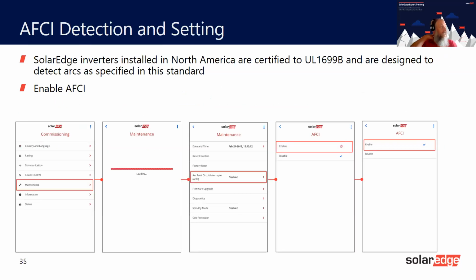Very easy to activate. You go to the commissioning screen in setup. If you're not familiar with that, we'll look at that later on. Go to the commissioning screen, go to maintenance, the screen pops up. You then have arc fault circuit interrupter, it's disabled. You click enable, it comes up enabled, and it's done. And you'll be able to see this in the status screen as well.